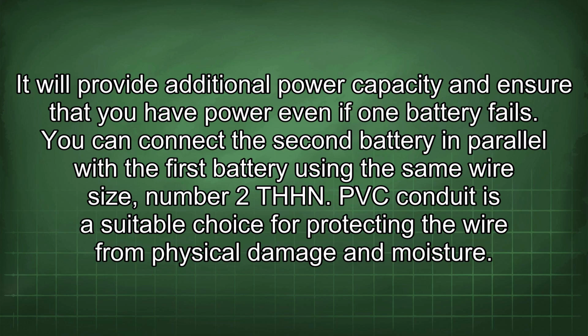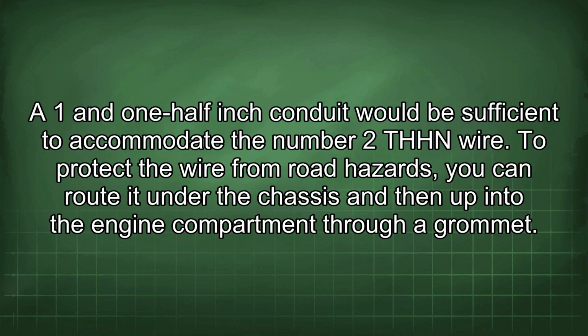You can connect the second battery in parallel with the first battery using the same wire size, number 2 THHN. PVC conduit is a suitable choice for protecting the wire from physical damage and moisture. A 1 1/2 inch conduit would be sufficient to accommodate the number 2 THHN wire.